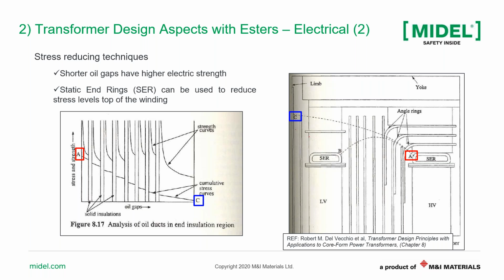Our interest usually is to really know where is the highest stress, usually at point A, and making sure that when we design for a synthetic ester instead of mineral oil, our stress at point A will not exceed the strength of the insulation. And this is more explained in the left-hand figure. In the left-hand figure, you can see on the x-axis oil gap and then pressboards, solid insulation, oil gap, and pressboards. And this is geometrically from point A to point C.